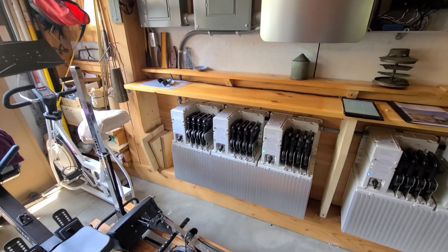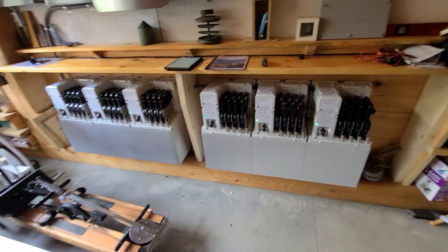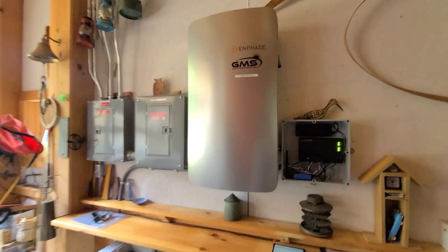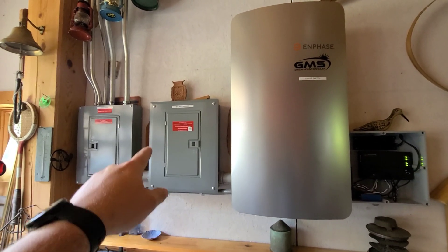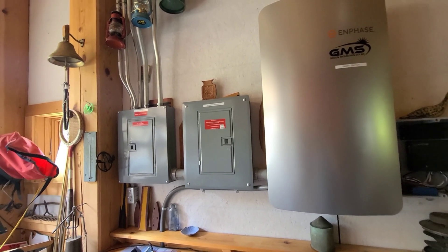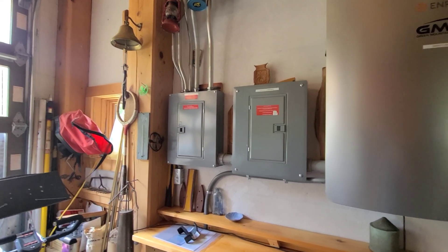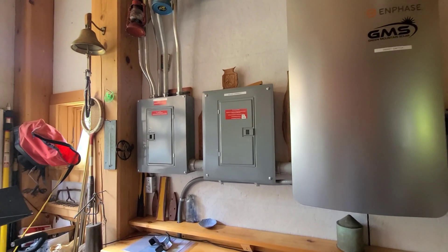I'm just working on getting this thing up and running right now. These are the batteries without the covers on them. This is two IQ Battery 10s, so just over 20 kilowatt hours. We have the smart switch over here, and this is the solar combiner. We had an existing Enphase array here and we added to it, so we're tying those two together in a regular load center, and then we have the output load center that feeds the house — it's just a small 100-amp service here.